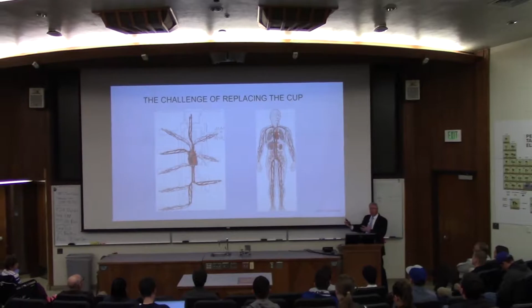And so the replacement CUP scope, we wanted to basically double the chilled water output. We were going to change the delta T. The delta T was the difference in temperature of water leaving the plant versus the return water, the temperature of the water when it was used and came back to the plant. We were going to close to double our hot water. We were going to generate about the same amount of electricity with our cogeneration system, but we were going to use that power internally. And we were going to take as much energy from the original natural gas that was used in the turbine to operate the plant and make it as efficient as possible. And one real big thing is we were going to substantially lower our emissions, which was a big issue for the Southern California Air Quality Management District. And we were going to have a new facilities management control system that was going to tie into the building automation systems that would be digital and would be much easier to manage.